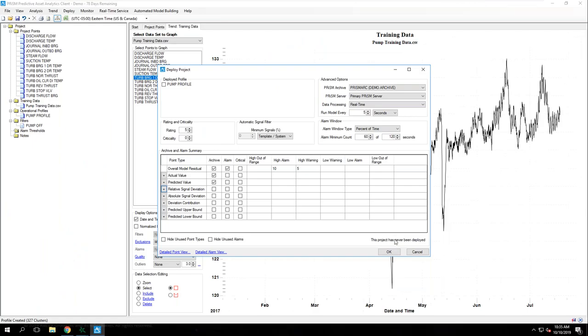I'm going to change that to 60 out of 120 seconds. That means our overall model residual has to reach 5% or 10% deviation from the predicted state for that time band—60 out of 120 seconds—before we'd actually generate any alerts or warnings. That keeps you from getting instantaneous nuisance alerts.